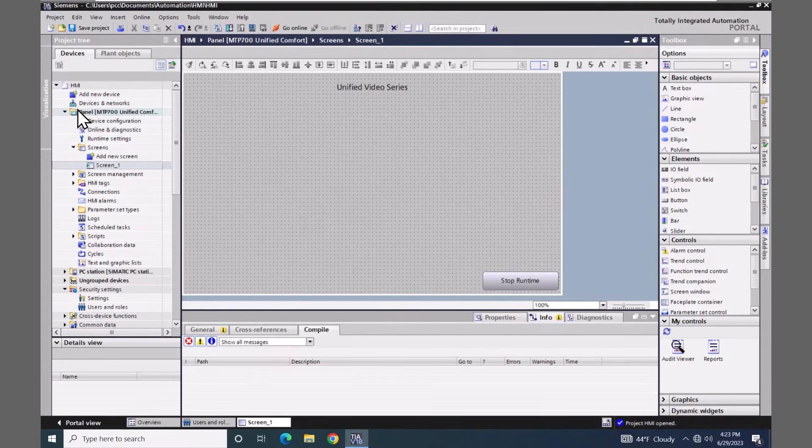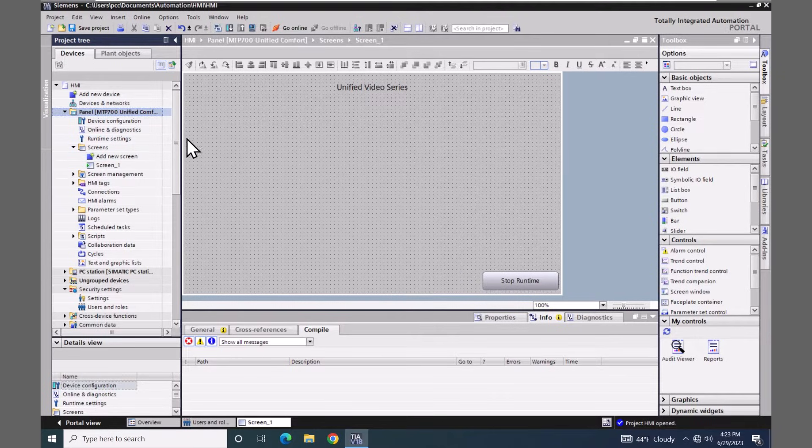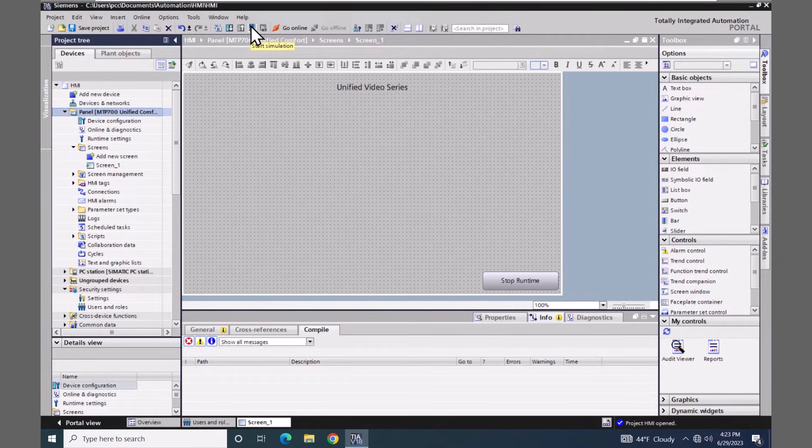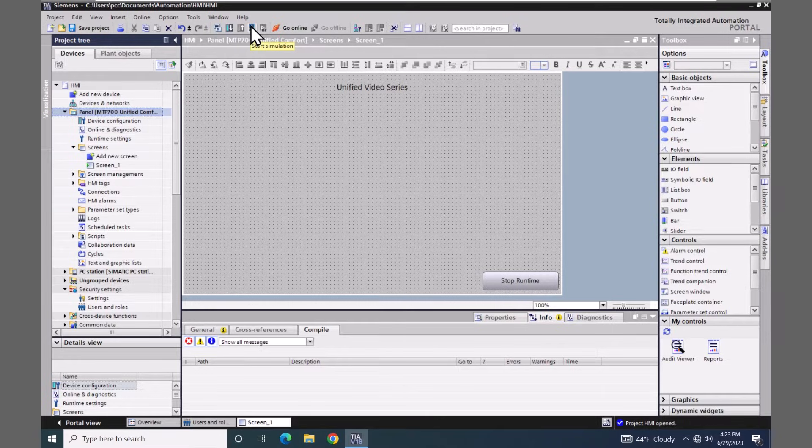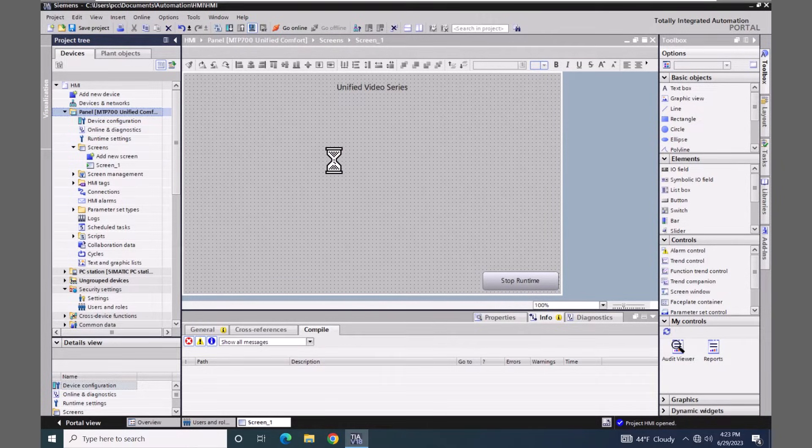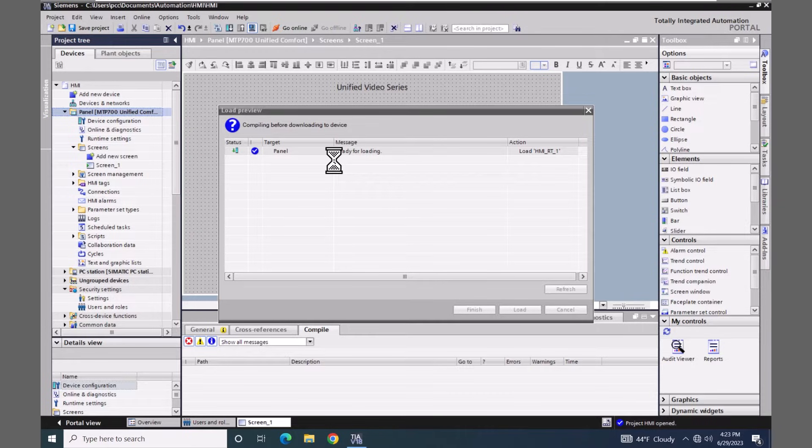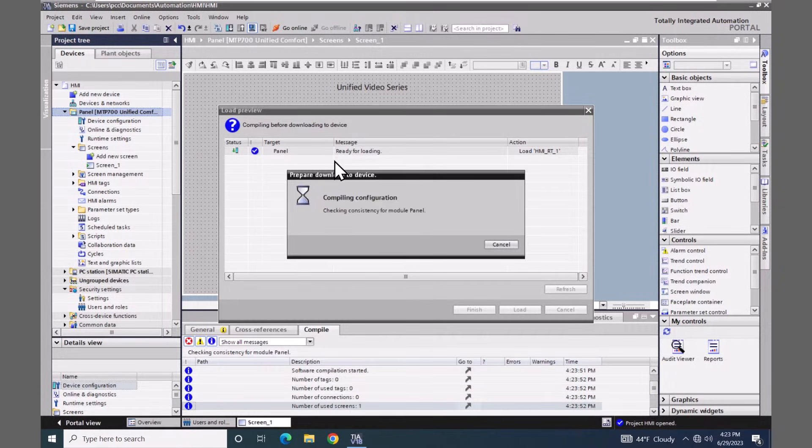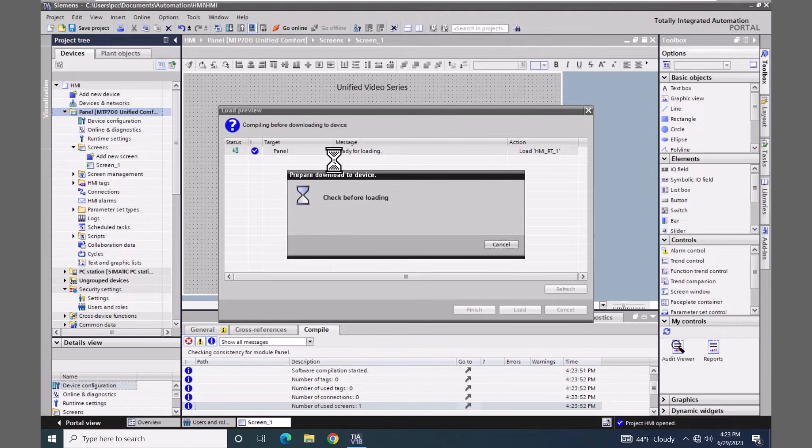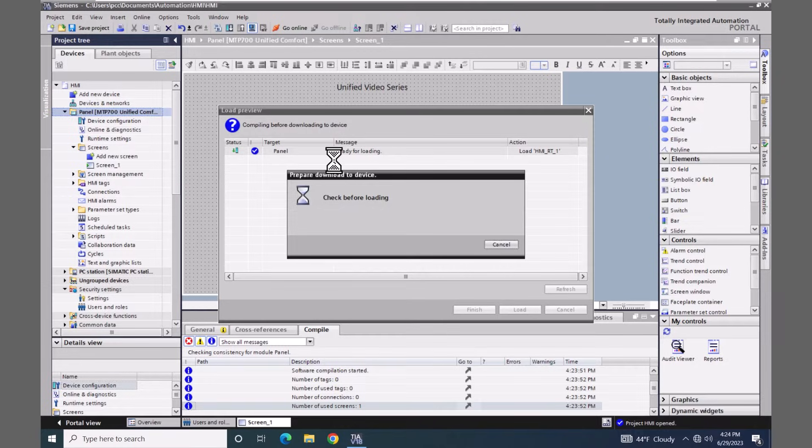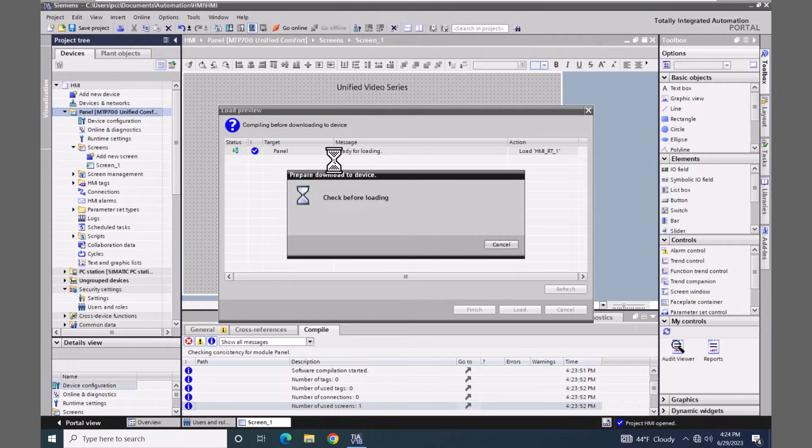I will select the HMI in the project tree. There's a button up on the toolbar that is the start simulation button. So I will select start simulation. This will start compiling the project. The project does have to be free of errors. You can simulate a project with warnings, but if you have errors, you will not be able to start the simulation.